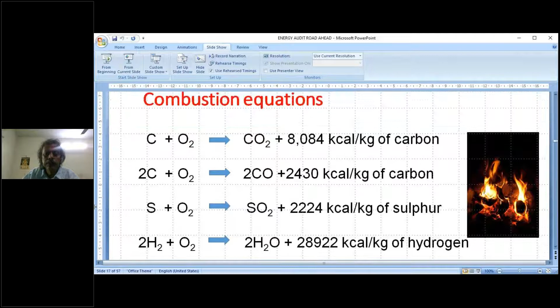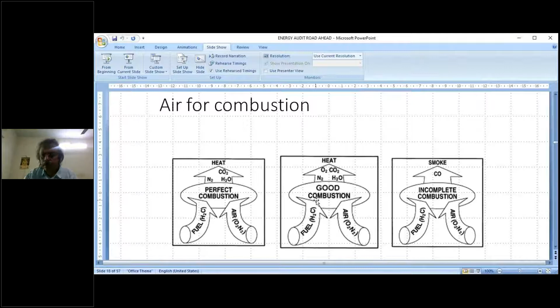One factor is how much air we give for combustion. Too much air means too much heat loss, too little air means unburnt fuel. So in between, there has to be a good combustion point where optimum air is provided to ensure complete combustion, minimizing losses. So we focus on this.